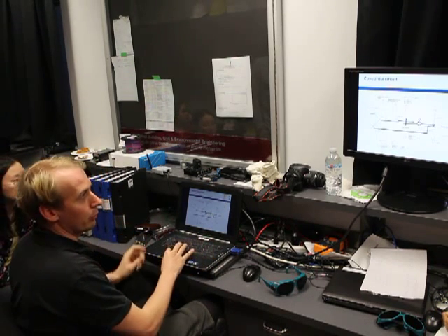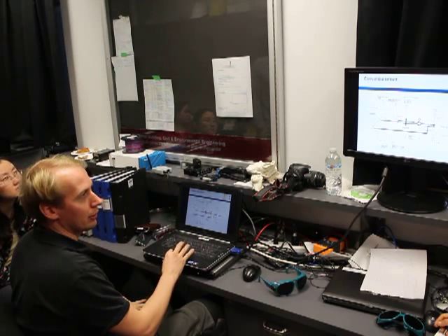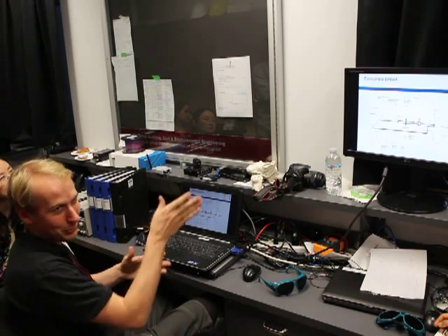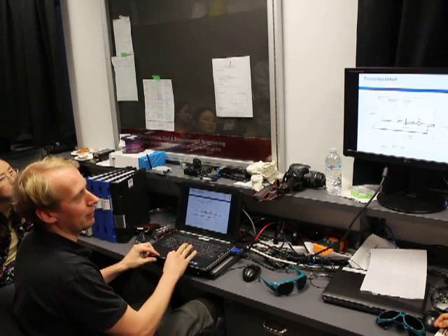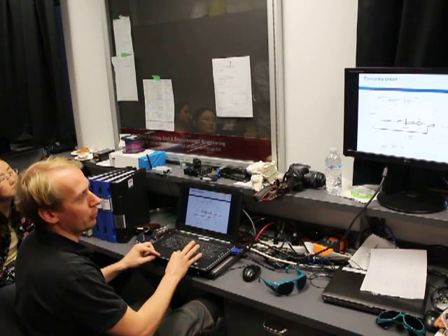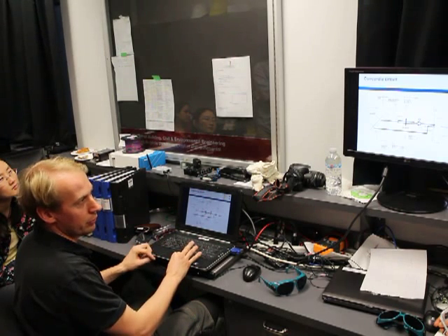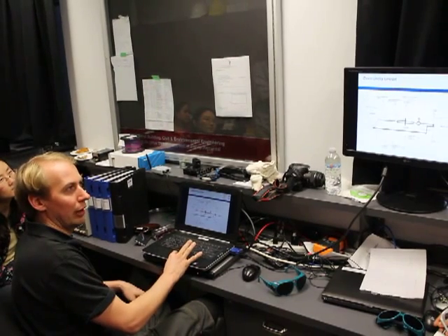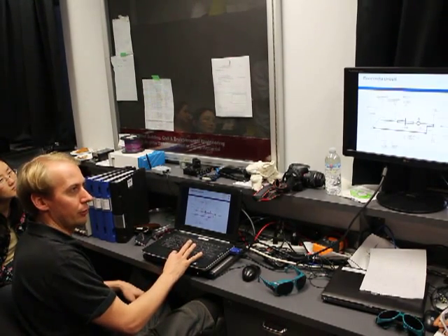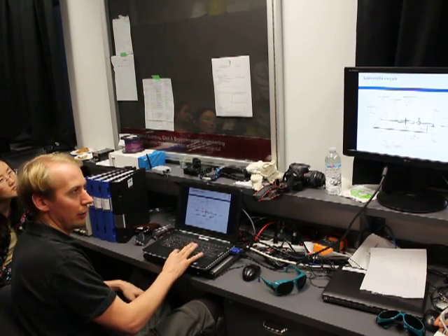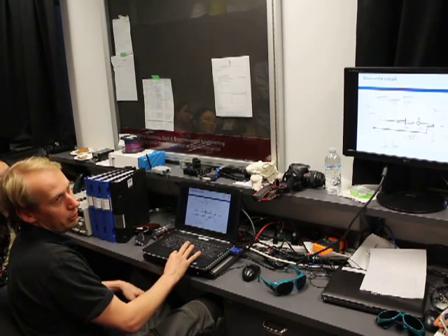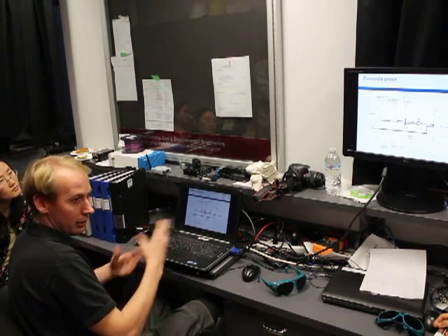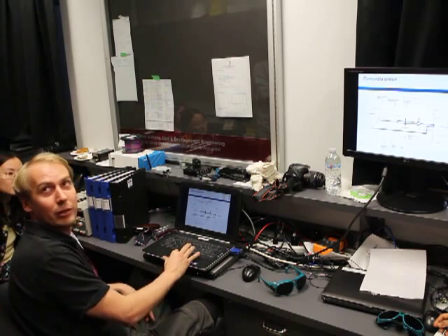So this is how we designed our closed loop system. The standard at that time was not ready, so this is the way we designed it back then. This is our mass flow meter. Here's our frequency transformer. This would be the air-water heat exchanger. You would take the temperature of the collector in to the heat exchanger, and here's the temperature of the collector out, in order to set the temperature of the water-air heat exchanger. In the end, you will have a gap, right?